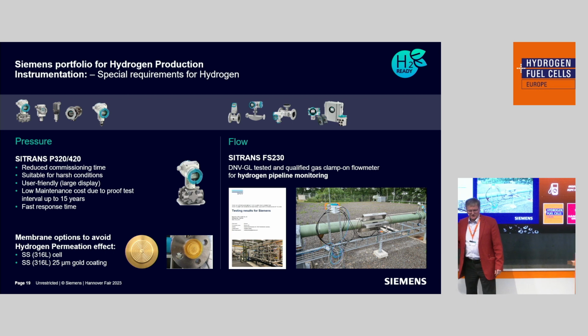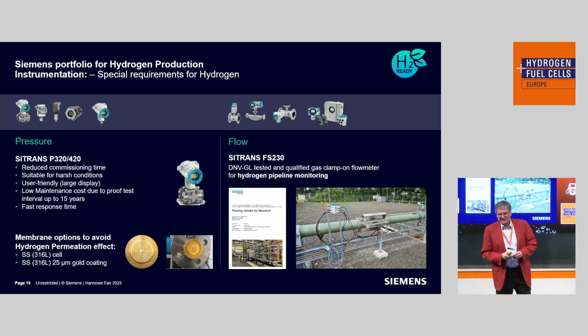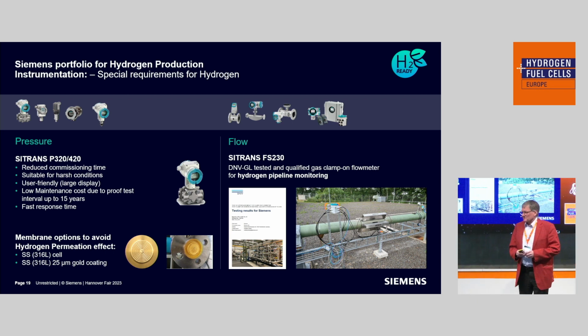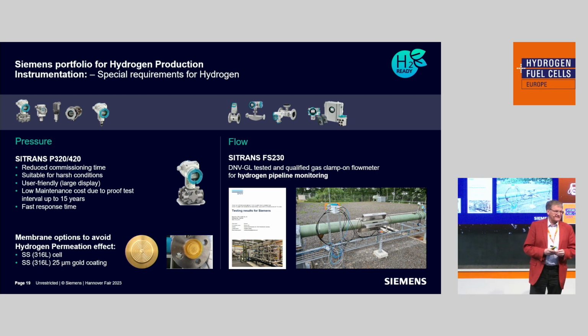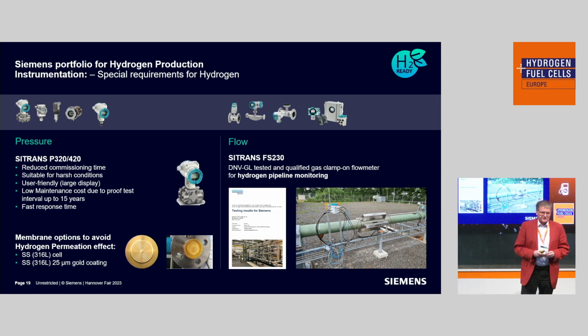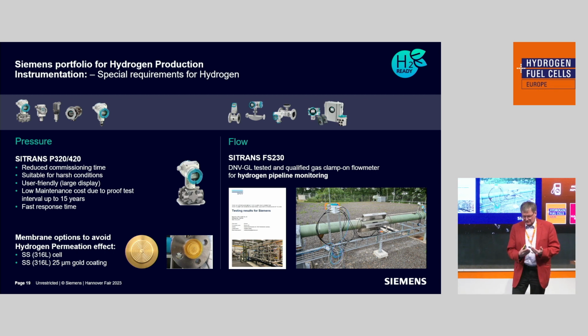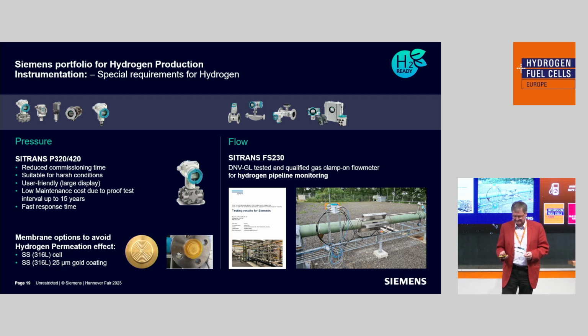For example, pressure transmitters now come with gold plates, because hydrogen permeates through metals that are otherwise gas-proof, which would build back pressure on those membranes, ultimately causing bad or inaccurate readings.